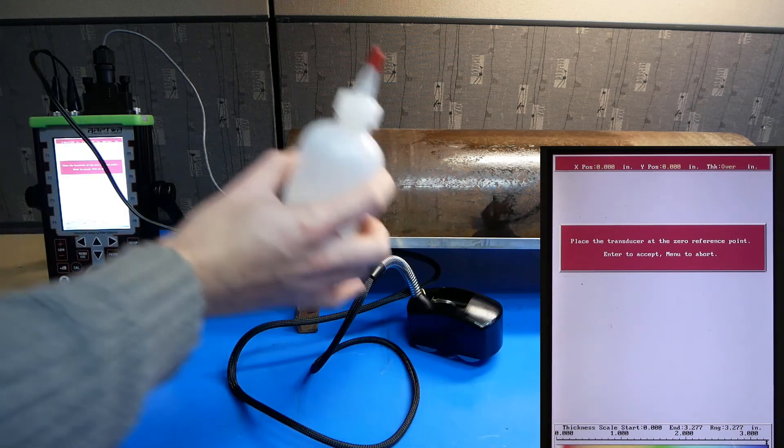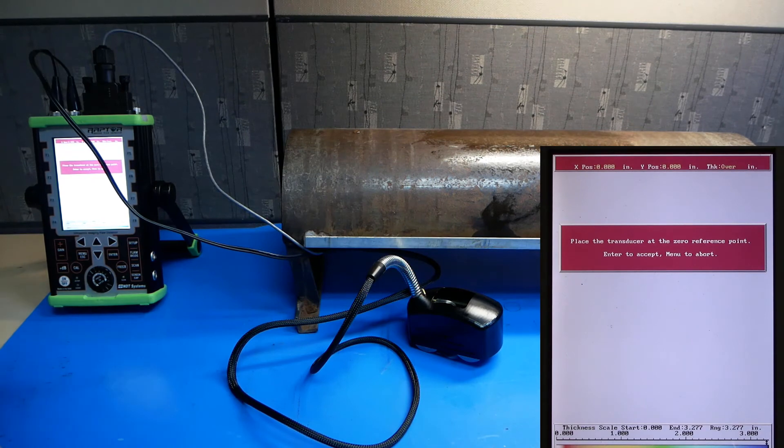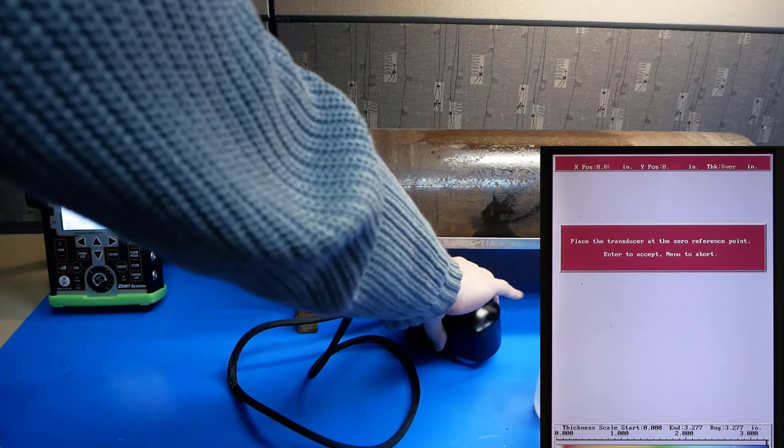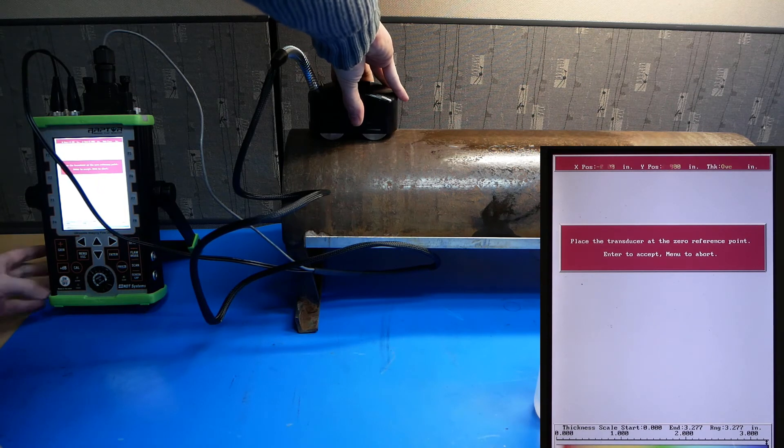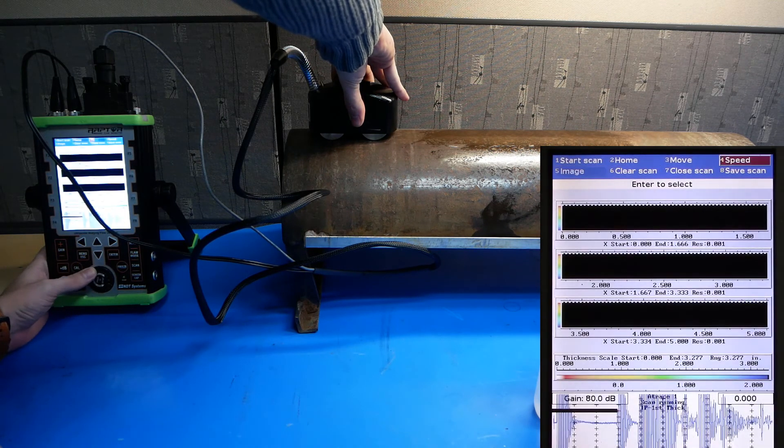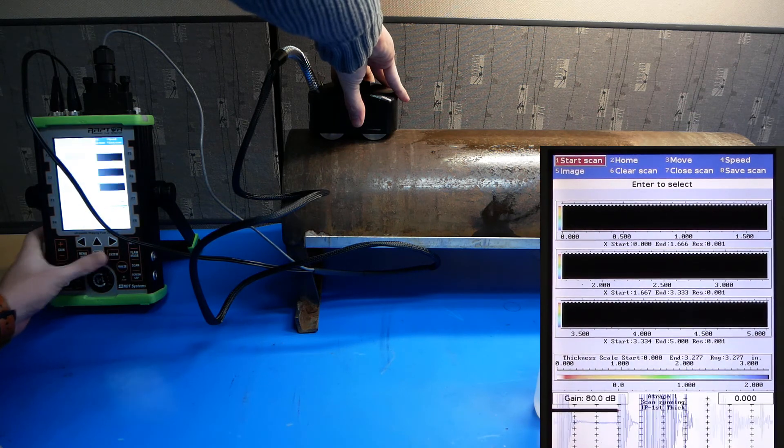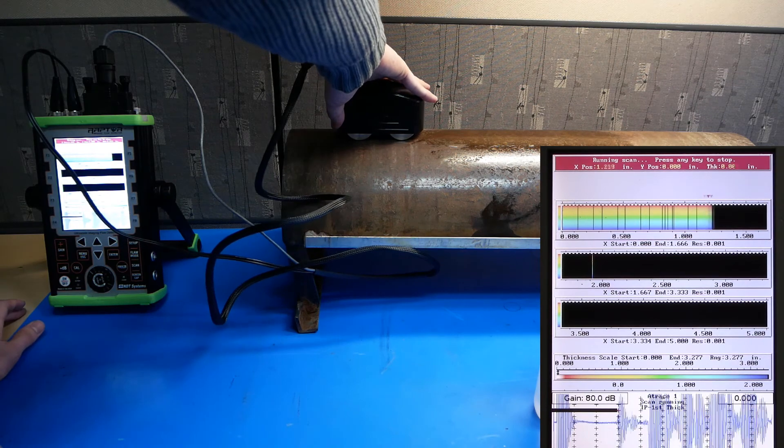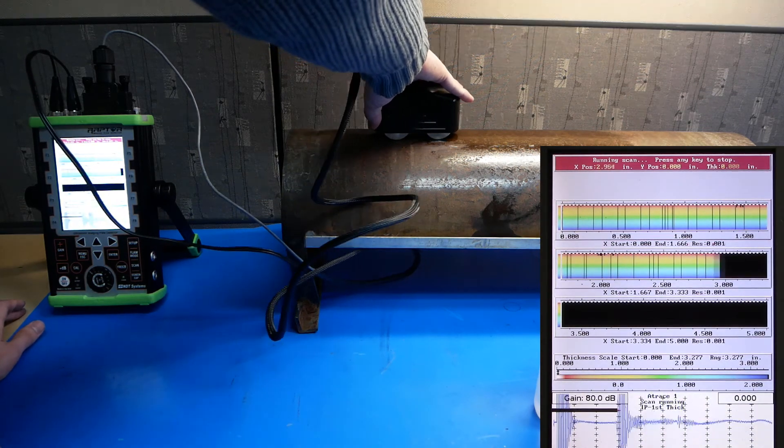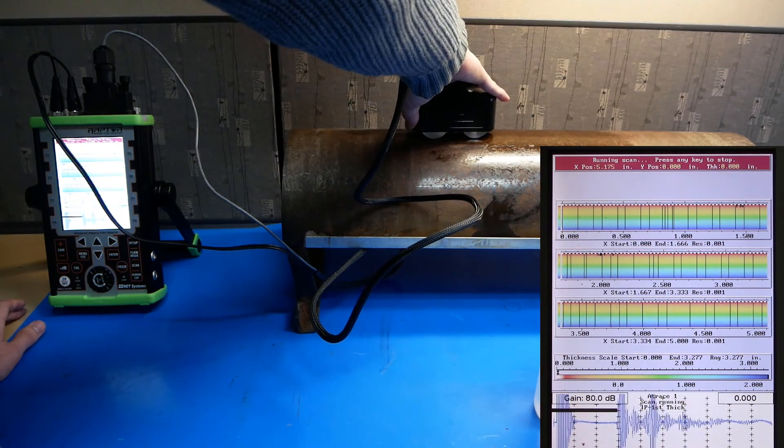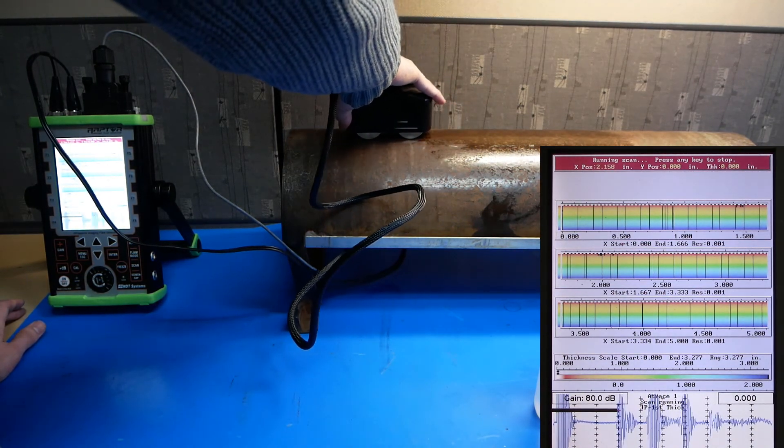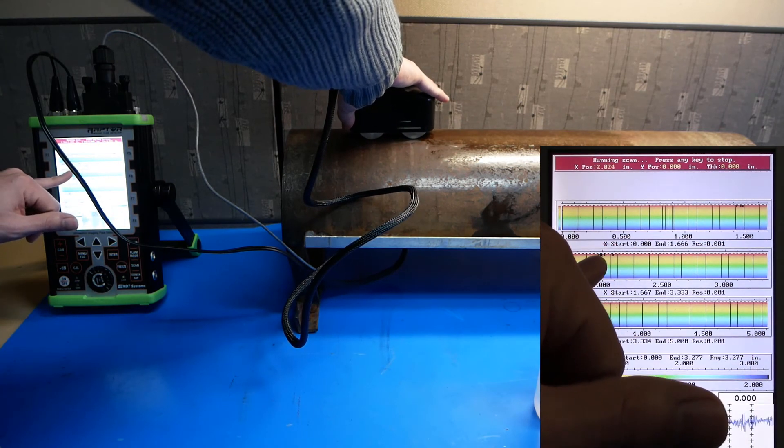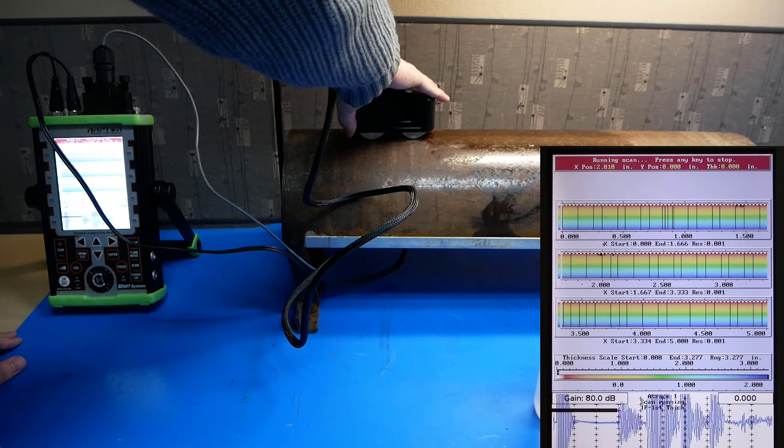Couple the probe to the test piece and place it at your starting point. Push enter when you're ready. Go to start scan. And feel free to move the Armadillo across the sample to find areas of corrosion. You can see here that there is a little bit of black at the top of the scan. That will indicate an area of pitting.